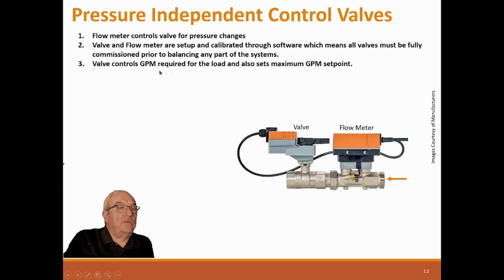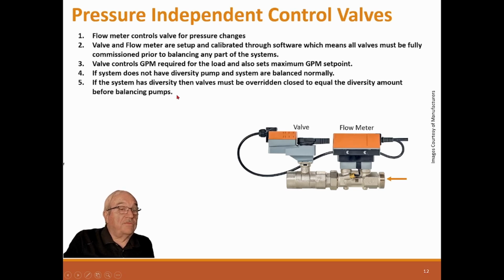The valve controls the GPM required for the load and also sets the maximum GPM set point. If the system does not have diversity, pumping systems are balanced normally, just like normal. If the system has diversity, then the valves must be overridden closed to equal the diversity amount before balancing the pumps. So this is just like any other system. You can't leave these in auto. If you've got diversity, some of these need to be closed.